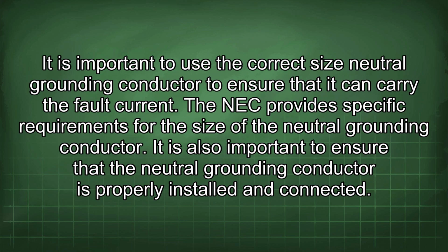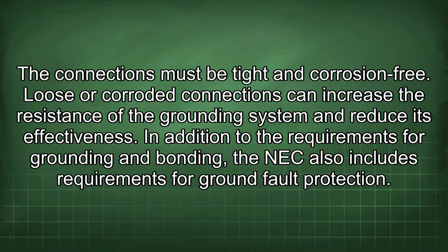It is important to use the correct size neutral grounding conductor to ensure that it can carry the fault current. The NEC provides specific requirements for the size of the neutral grounding conductor. It is also important to ensure that the neutral grounding conductor is properly installed and connected. The connections must be tight and corrosion-free. Loose or corroded connections can increase the resistance of the grounding system and reduce its effectiveness.